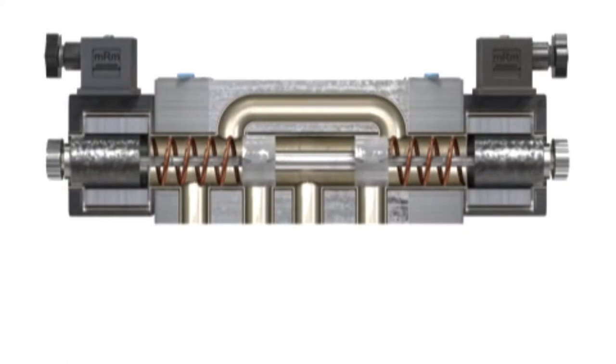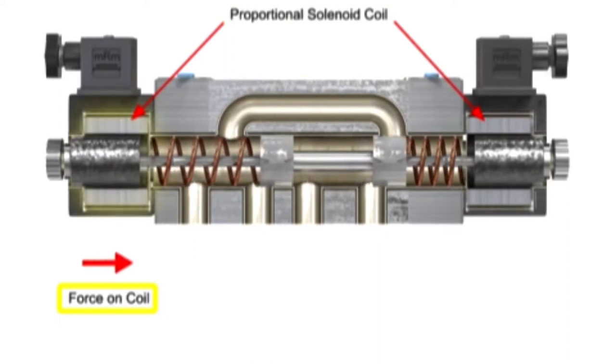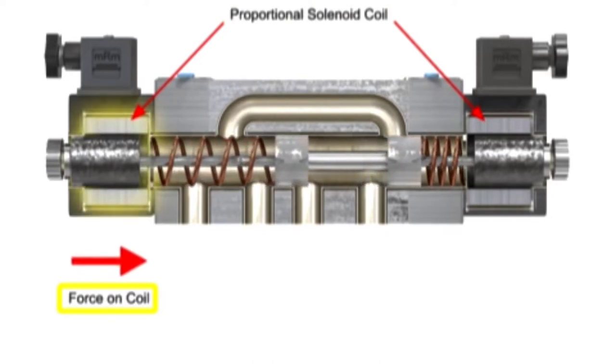Physically, proportional valves appear similar to their on-off solenoid counterparts. The big difference is in the way their solenoid coils perform. Proportional coils operate on DC current and produce varying currents that in turn produce a variable force to shift the spool.